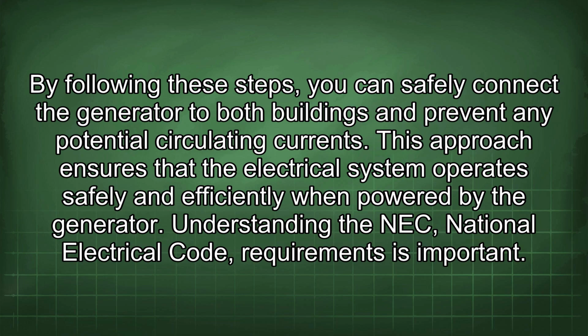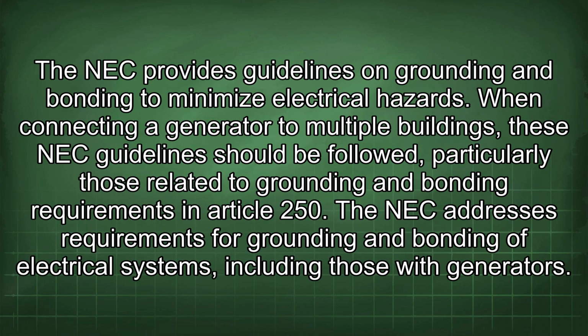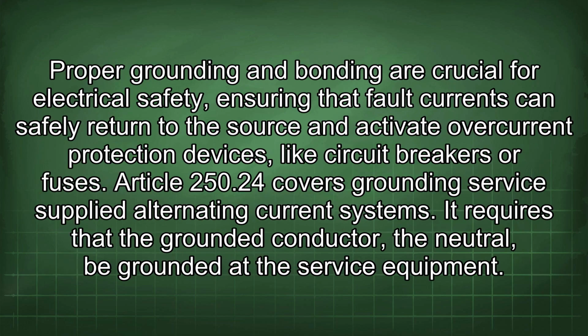Understanding the NEC, National Electrical Code, requirements is important. The NEC provides guidelines on grounding and bonding to minimize electrical hazards. When connecting a generator to multiple buildings, these NEC guidelines should be followed, particularly those related to grounding and bonding requirements in Article 250. The NEC addresses requirements for grounding and bonding of electrical systems, including those with generators. Proper grounding and bonding are crucial for electrical safety, ensuring that fault currents can safely return to the source and activate overcurrent protection devices like circuit breakers or fuses.